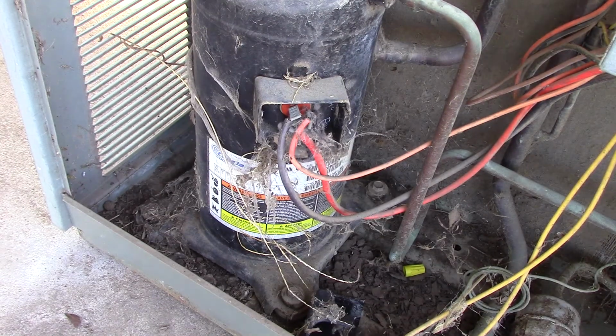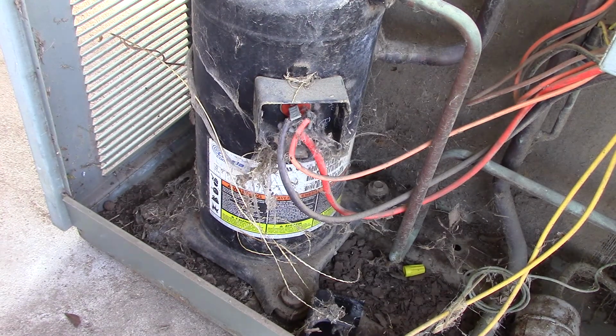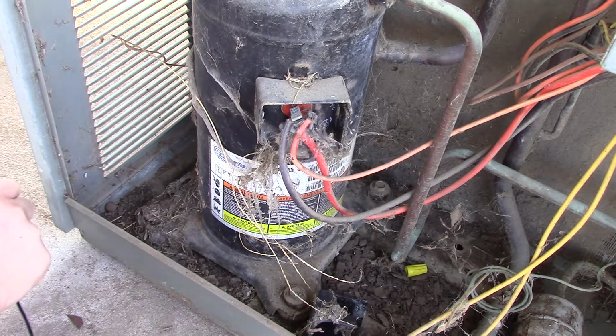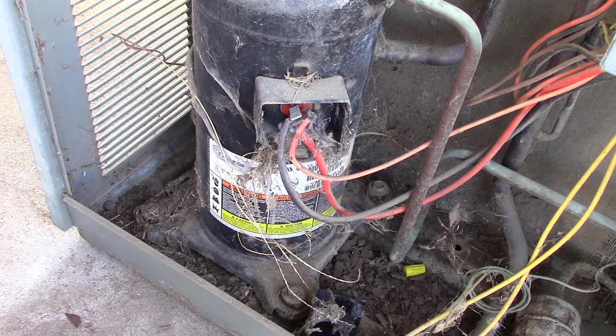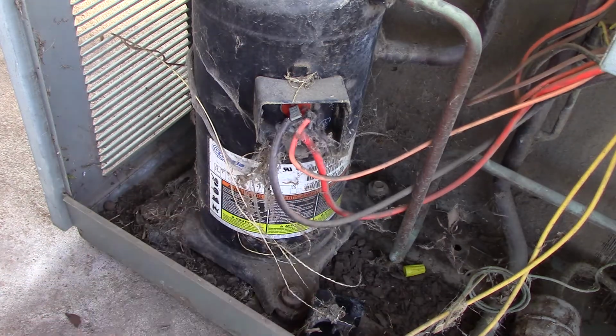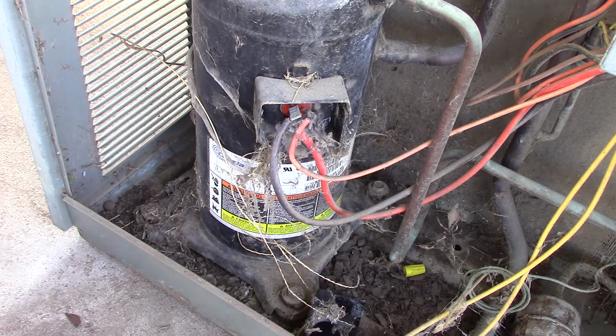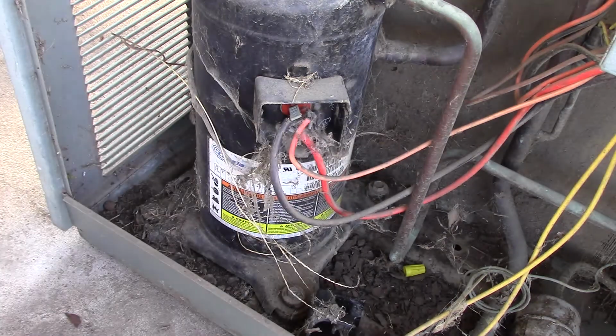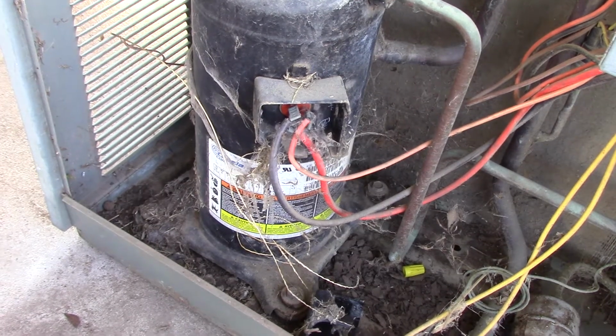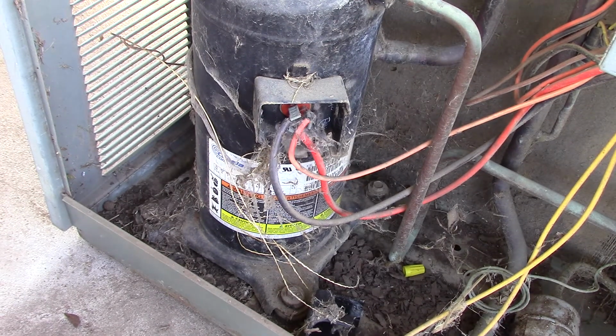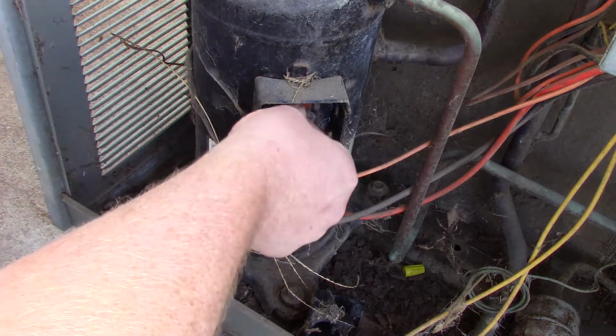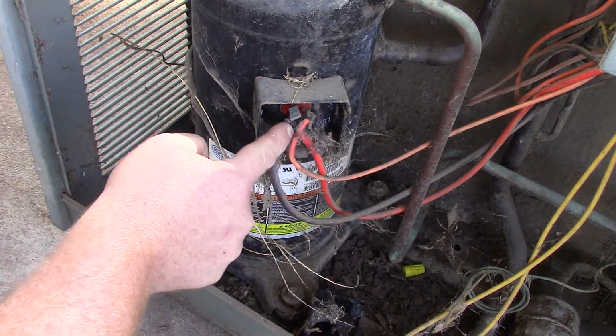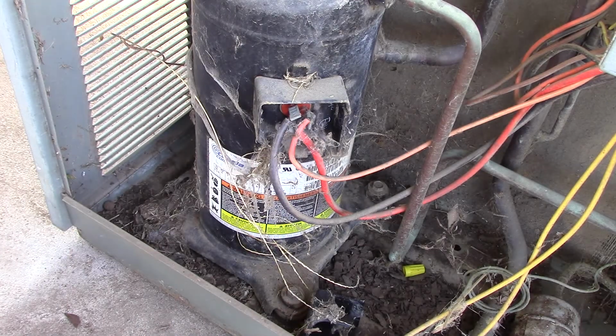One, those terminals are a safety, as in if overpressurization happens in the system, this is your pressure relief. So those terminals can blow out. You go to remove these wires, be careful with it. Don't yank, jerk, or wiggle as hard as you can, because you can actually break those terminals. And if you break them, well, you're in a whole new mess right there. So carefully remove those plugs. You can have your run, common, and start to ohm out the compressor there.